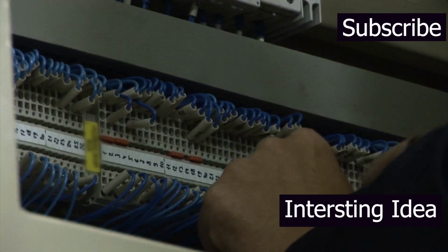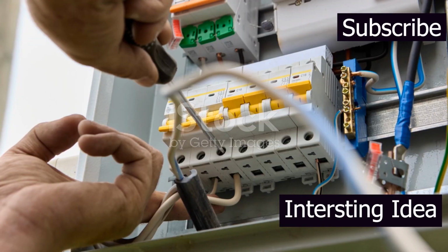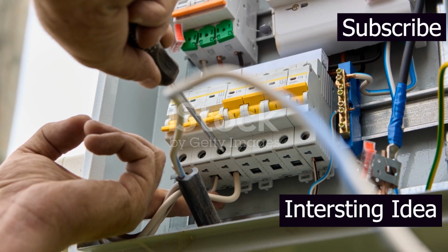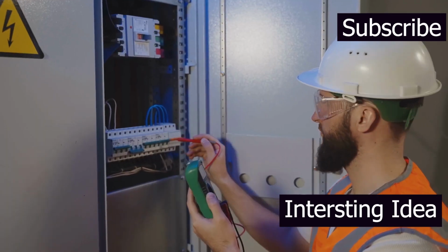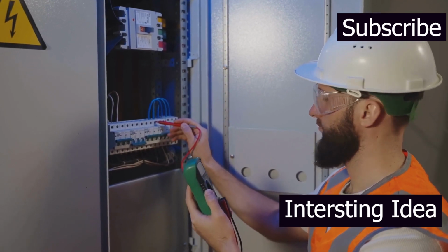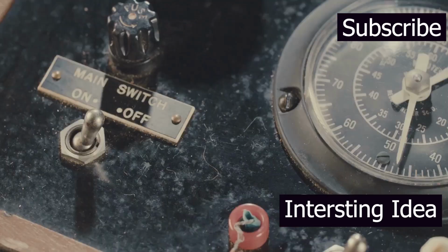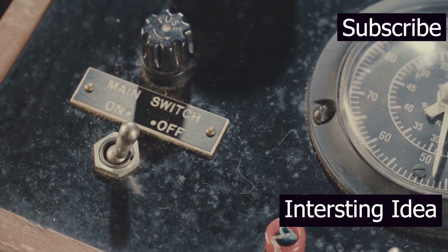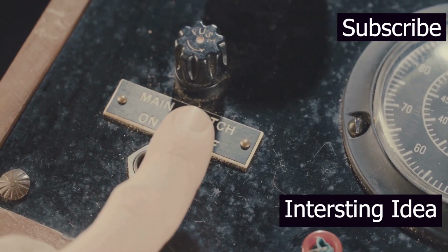Section 8. Safety first. Testing your panel. Before you call your panel complete, it's essential to test it thoroughly. This step ensures all connections are correct, the breakers are functioning properly, and your system is safe to use. Use a voltage tester to check that there is no voltage present at the panel before you begin. Then, carefully turn on the main breaker and check that the panel is receiving power.